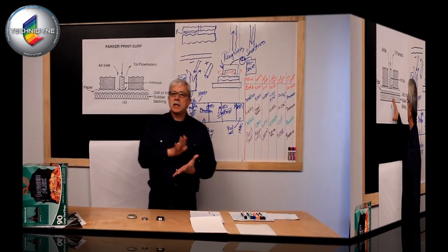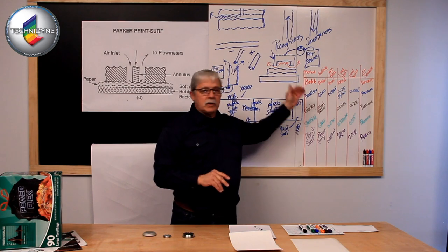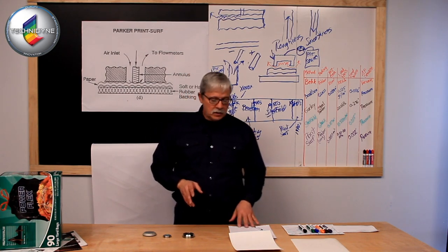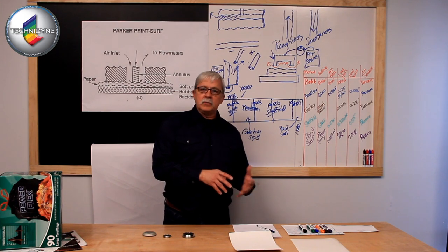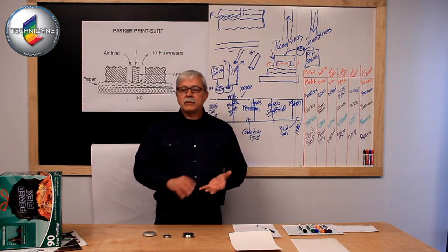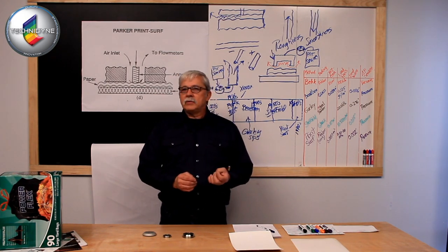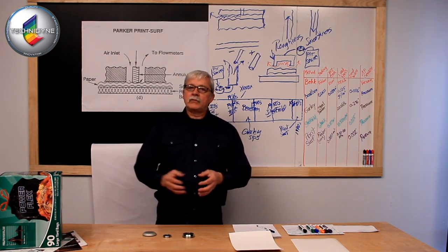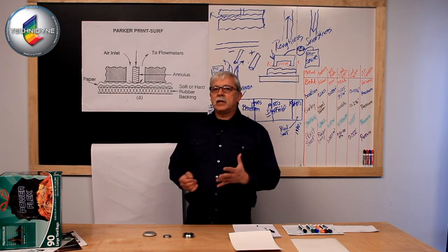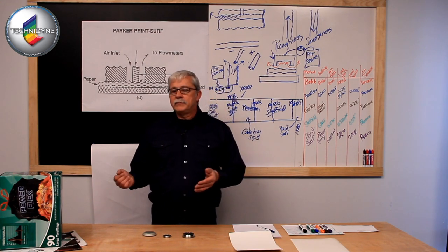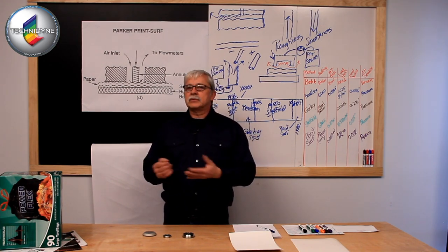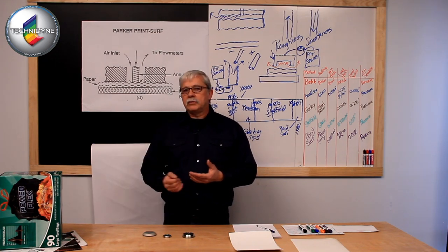Okay, so we've got a sandwich that's very similar to all of our other methods. We've got a pressure differential and now we need a means to actually measure that air flow. So when we look at measuring air flow previous to this, we describe some volume that you measure. So you have a rate based on a volume. We had rotameter tubes that actually measured the flow through the system. And in this particular case, what he decided to do was to take another approach and actually use differential pressure to measure the air flow through a particular system. And there's a very good relationship between change in differential air flow, sorry, differential pressure and the rate of flow that's moving through your system.